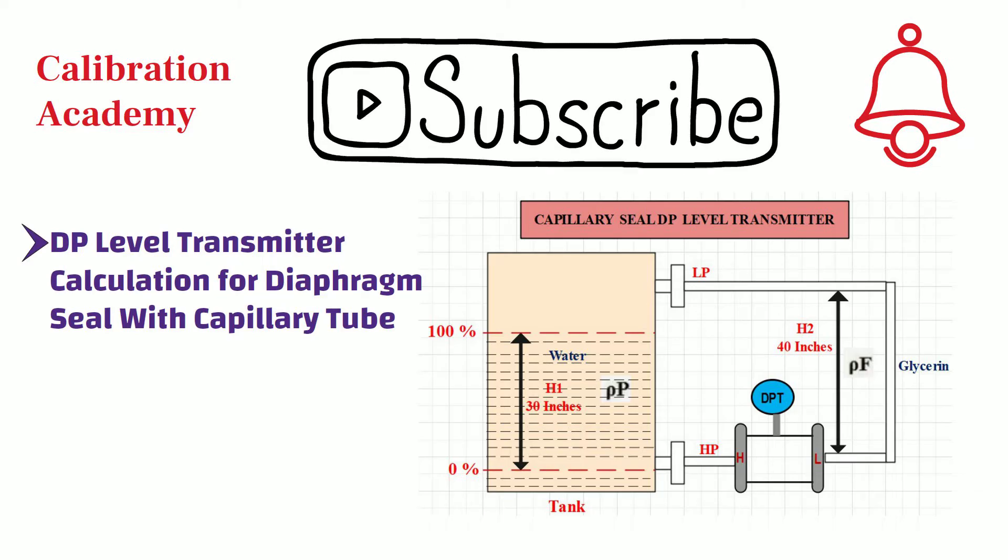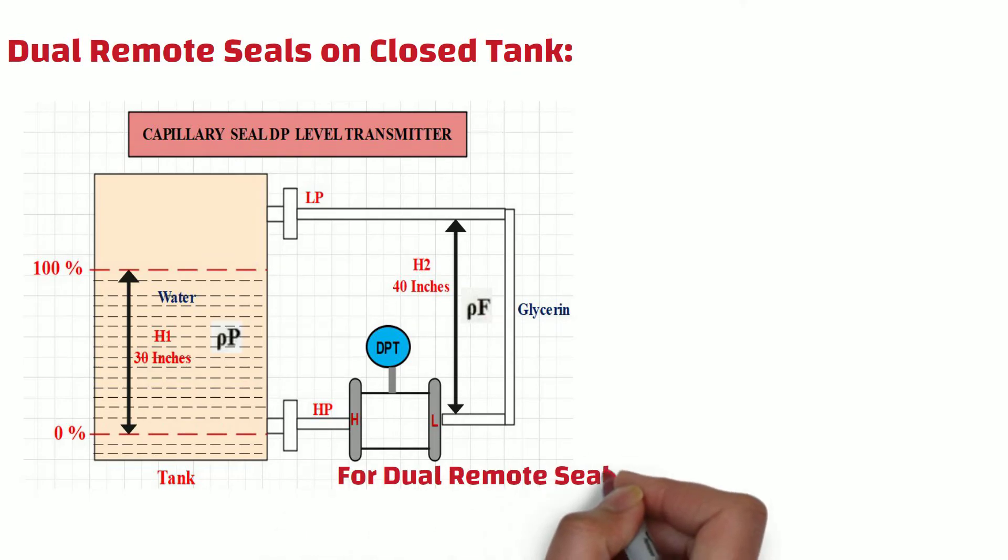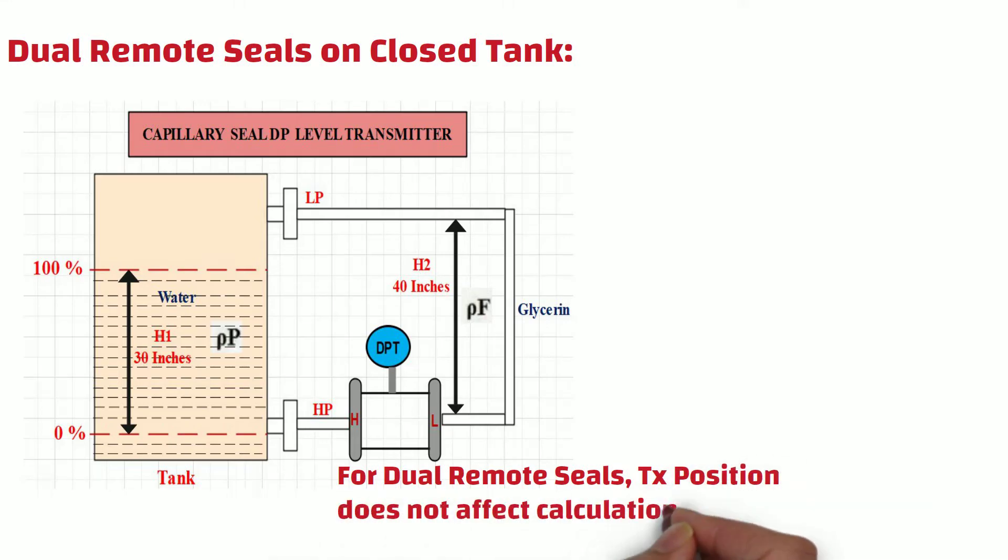Now, let's go to the calculation. As you can see from the diagram, this is an example of dual remote diaphragm seal on a closed tank. First of all, it is important to understand that the transmitter position does not affect the calculation when dual remote seals are used. In other words, it does not matter whether the transmitter is at, below, or above the bottom tap when dual remote seals are used. The LRV and URV are the same for all three conditions.